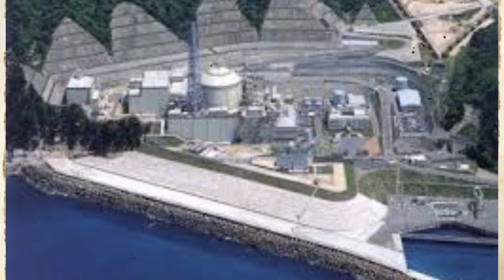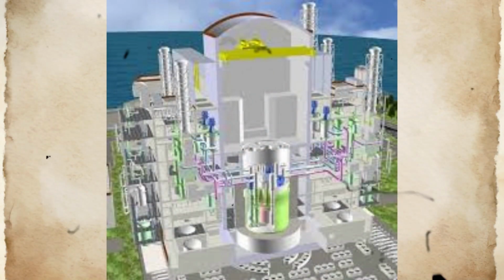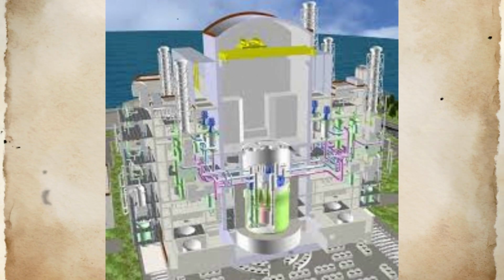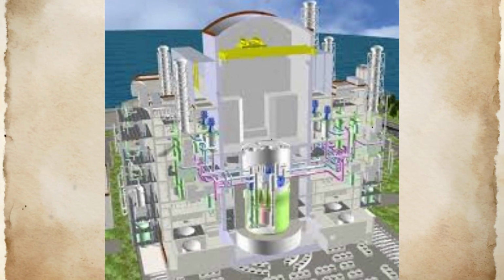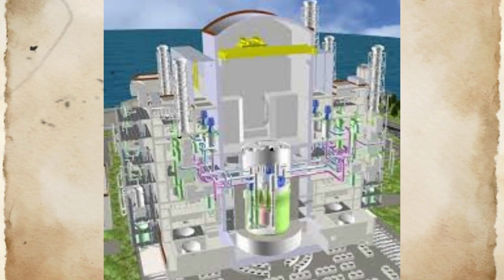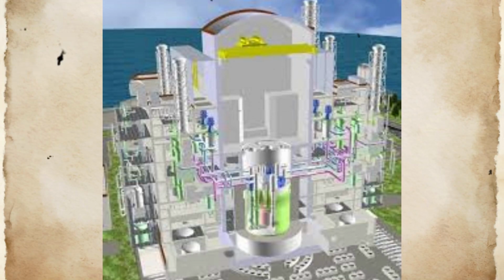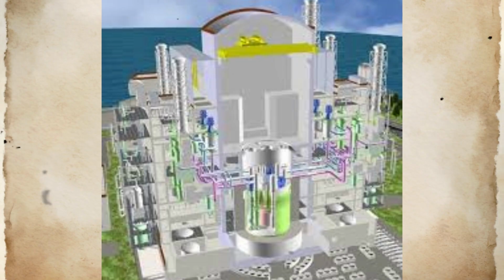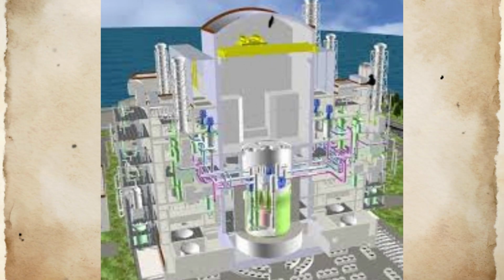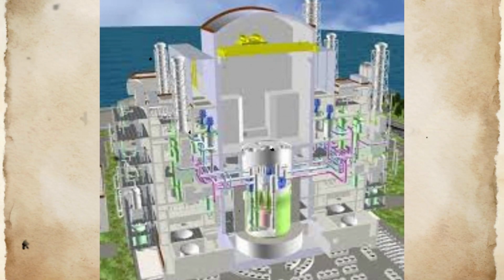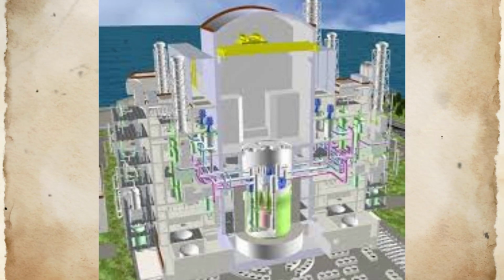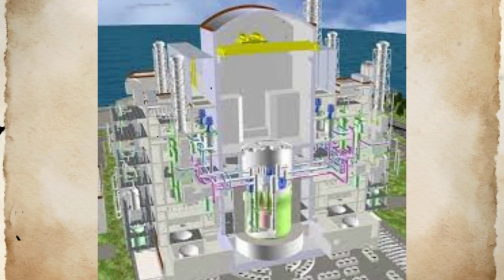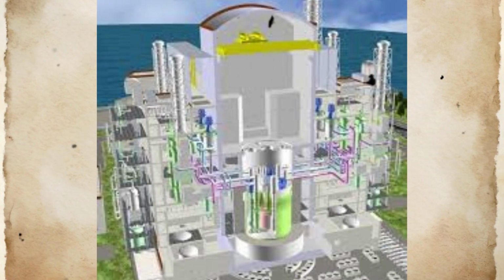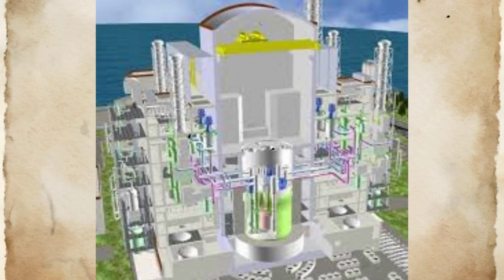The discovery location confirmed that the separated tip had been transported through the secondary loop piping by sodium flow, eventually coming to rest in a region where flow velocity decreased sufficiently for the component to settle. Recovery of the separated tip using a specially developed gripper on April 24, provided physical evidence that confirmed the failure mechanism analysis. The recovered component exhibited fracture surface characteristics consistent with fatigue failure, validating the theoretical analysis of flow-induced vibration and stress concentration effects.